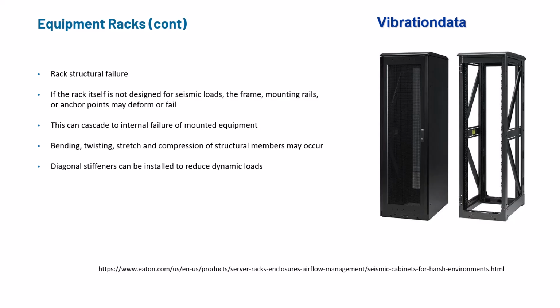Then the racks. We want good quality racks, as rack structural failure is a possibility. If the rack itself is not designed for seismic loads, the frame, mounting rails, or anchor points may fail, and this can cascade to other types of internal equipment failure. So just think about your basic engineering: bending, twisting, stretching, shear forces, compression, buckling.